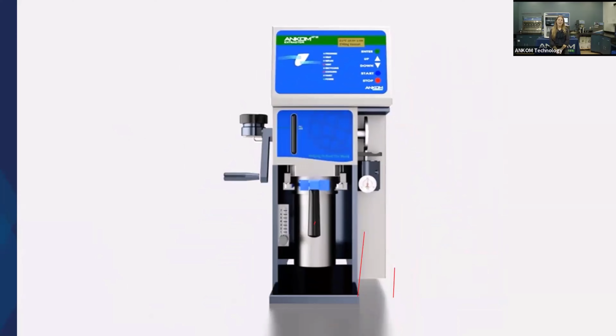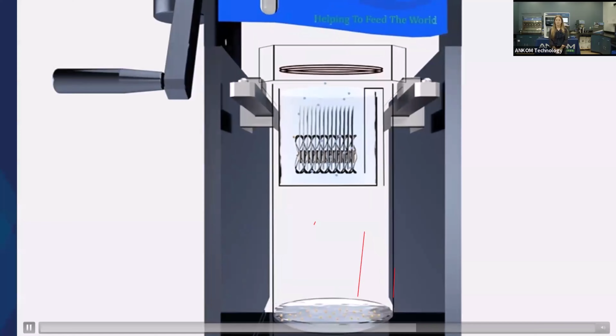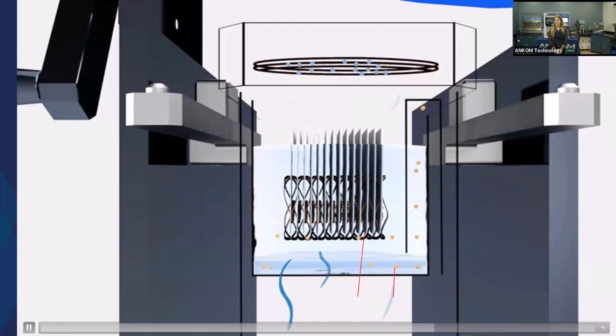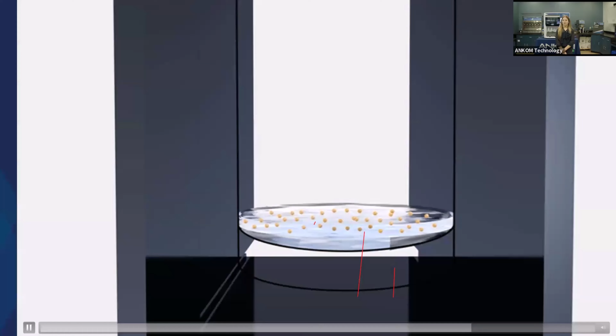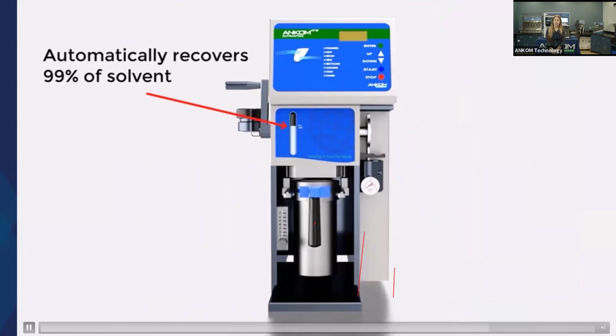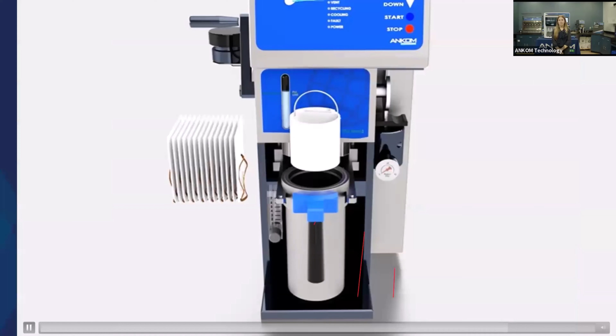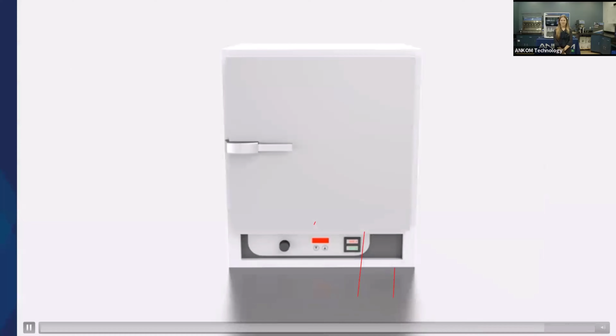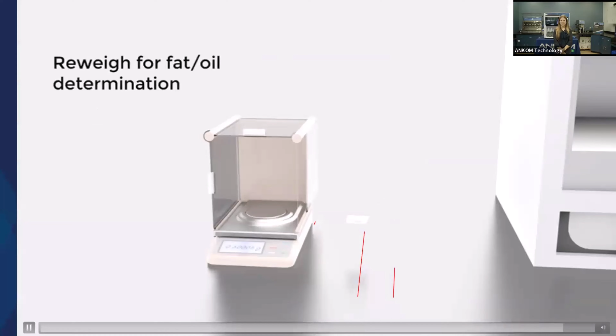Solvent is automatically inserted, heated, and refluxed at high temperatures under pressure. Using a high-temperature process, lipid components are rapidly removed from the sample, while non-lipid components remain during a reflux operation. Throughout the operation, the solvent refluxes and siphons throughout the selected time, ensuring that each sample is completely extracted. At the end of the cycle, the solvent is automatically distilled and recycled, ready for automatic reuse in the next extraction run. The filter bags are placed in an oven for a short final drying, and then re-weighed to determine the amount of fat or oil the sample contained.